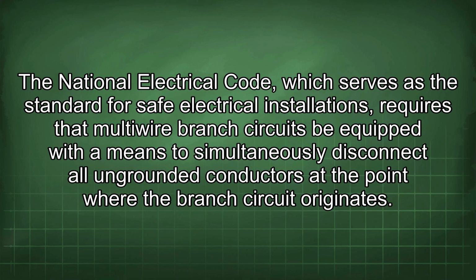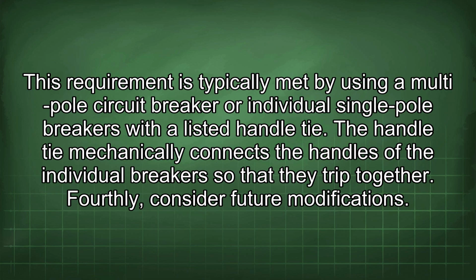The National Electrical Code, which serves as the standard for safe electrical installations, requires that multi-wire branch circuits be equipped with a means to simultaneously disconnect all ungrounded conductors at the point where the branch circuit originates. This requirement is typically met by using a multi-pole circuit breaker or individual single-pole breakers with a listed handle tie. The handle tie mechanically connects the handles of the individual breakers so that they trip together.